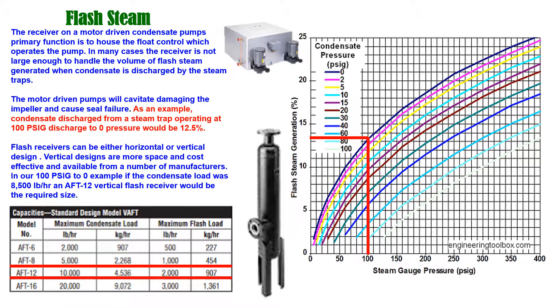When flash steam is condensed and discharged through a steam trap to a lower pressure, a portion of the condensate will flash into steam at the lower pressure. As shown in red on the chart, steam at 100 psig will generate about 12.5% flash steam at atmospheric pressure.